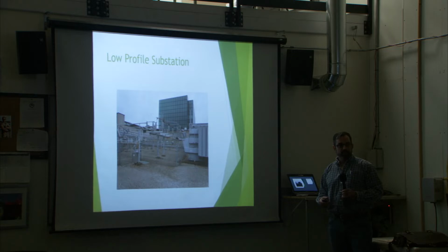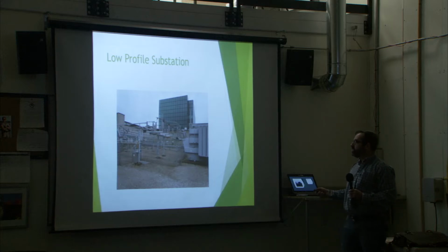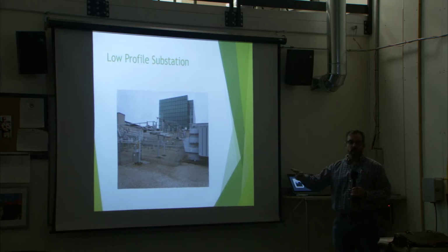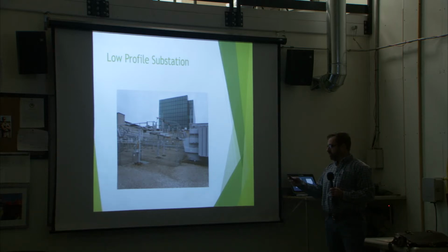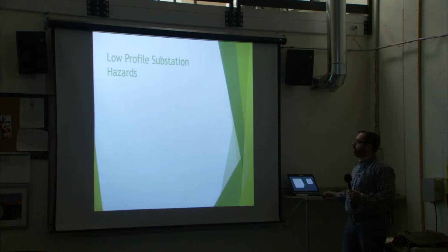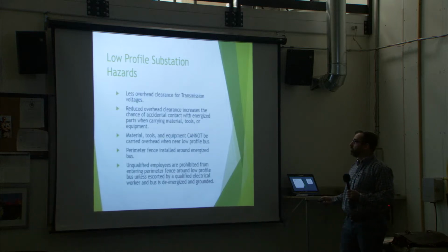Okay. Tainer, White Oaks, Tansy. Any of these substations that contain low profile bus will have a perimeter fence around all of the bus work. So it's not like you can just walk into a sub with low profile bus and walk right up to the bus work itself. There are some unique hazards associated with low profile stations.